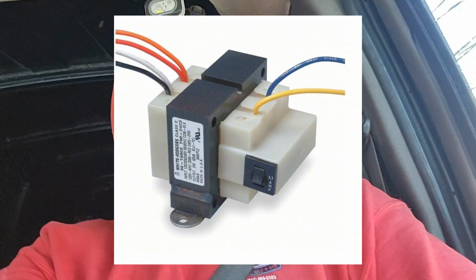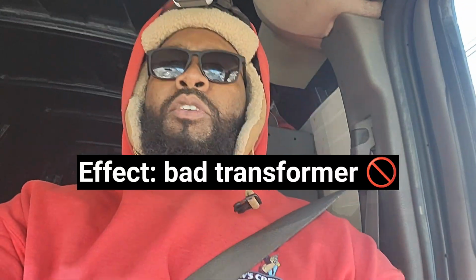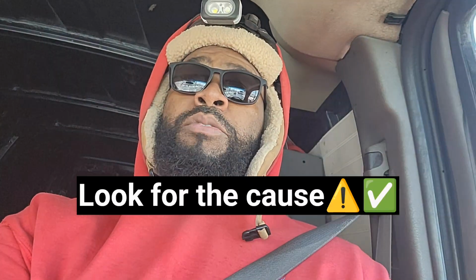I am on the way to the supply house. Now, guys, the moral of the story is whenever you're out here troubleshooting transformers, always look for the cause. The effect, of course, would be a bad transformer, but you have to realize transformers always fail due to a shorted wire. They don't fail just to fail. So, guys, always look for obvious signs of burnt wires or even miswiring.